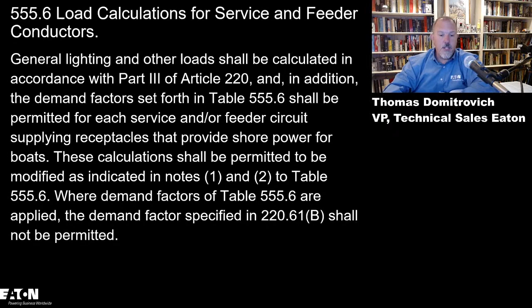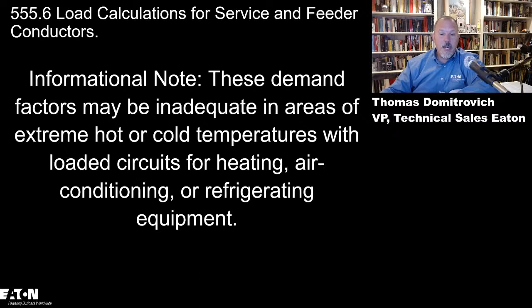And there's demand factors in here, and they'll tell you that those demand factors may be inadequate in areas where it's extremely hot or cold temperatures, because you have heating and air conditioning and possibly refrigeration equipment where? On the boats, right? You saw that one air conditioning unit and a freezer on that one pontoon boat. So you got to be mindful that this stuff is going on inside, in and around those marinas.